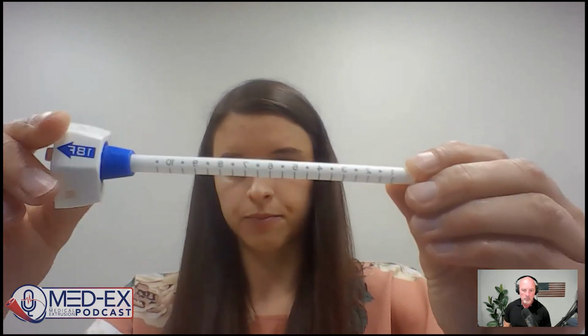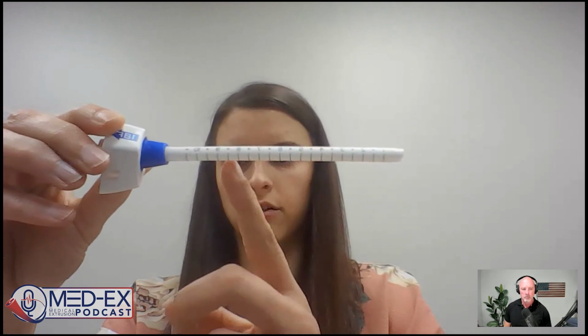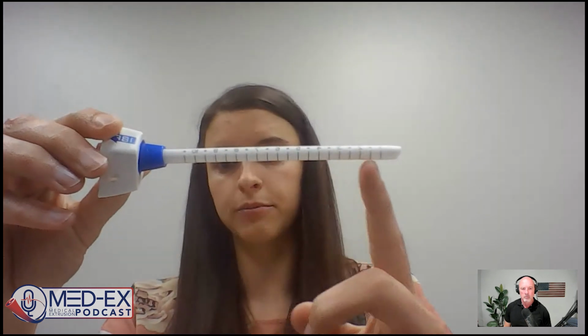So I got a device here that's got some depth marks in it. And the UV laser marker is actually datumed off the tip here. And so the vision system will zero off the tip. And so these are held to a very precise tolerance in terms of the depth location. These marks can be anything from depth marking similar to that part, logos, French sizes, etc.